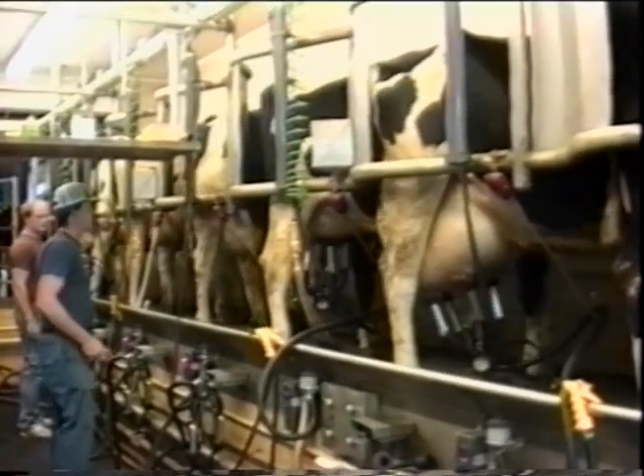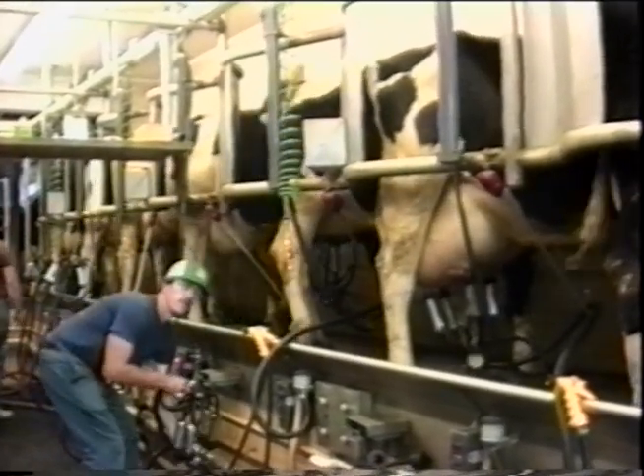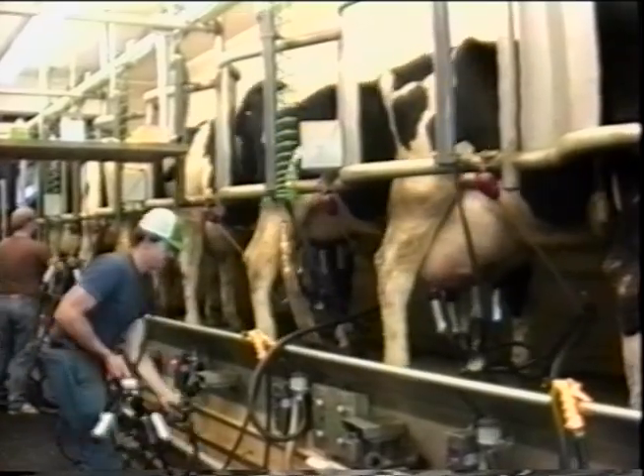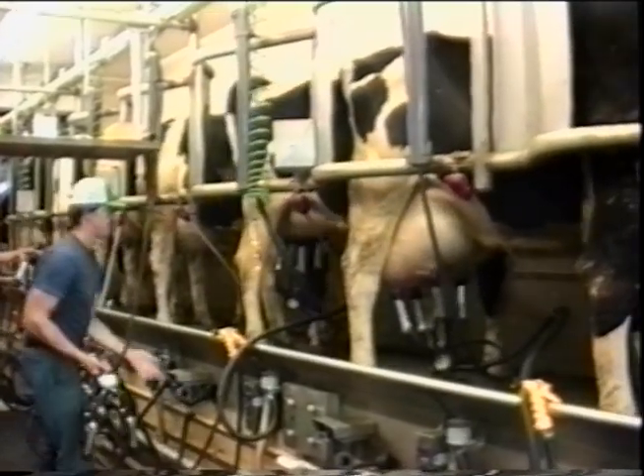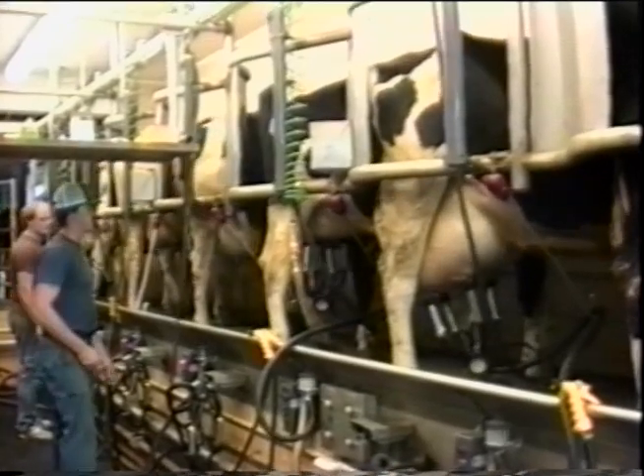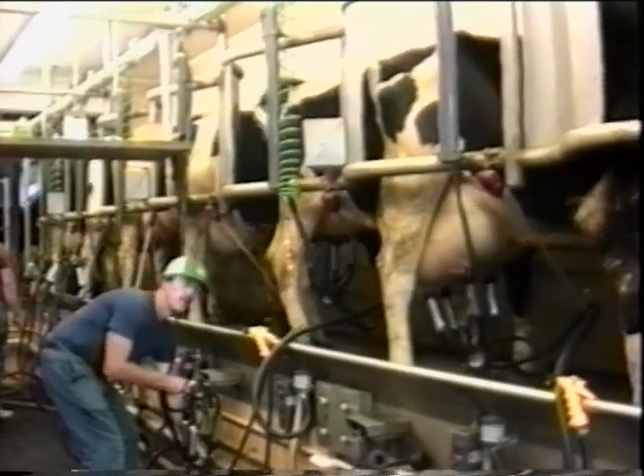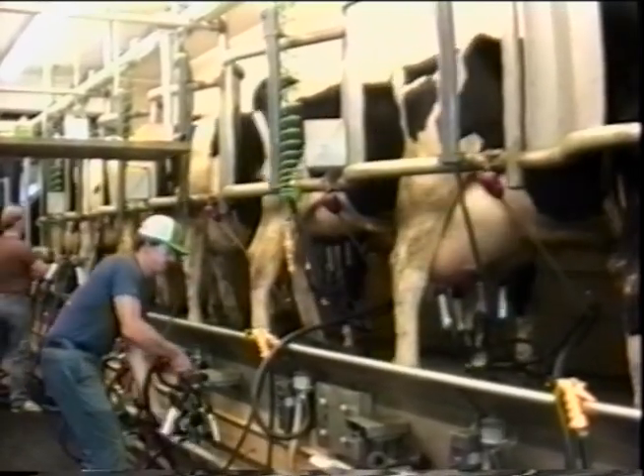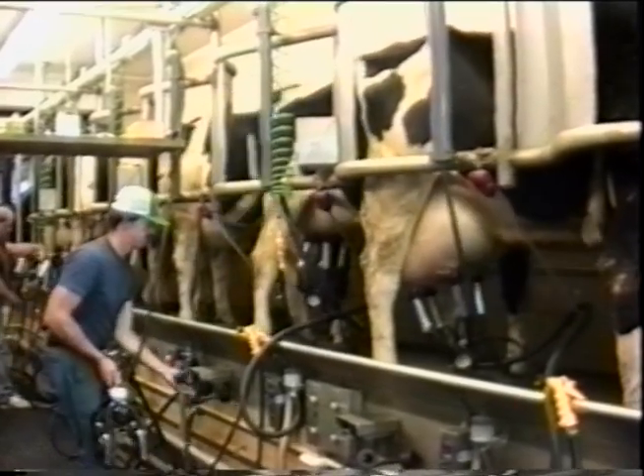This outstanding dairy herd in central Michigan was dancing because uncontrolled electricity on the ground wire was traveling through concrete and metal stalls, shocking cows and interrupting the milking process. The problem was solved when the utility was required to move the transformer pole out of the barnyard and a neutral isolation transformer was installed between the utility and the dairy farm electrical system.